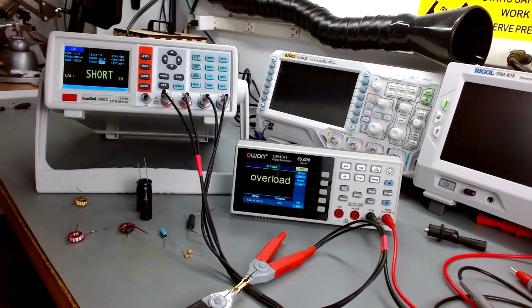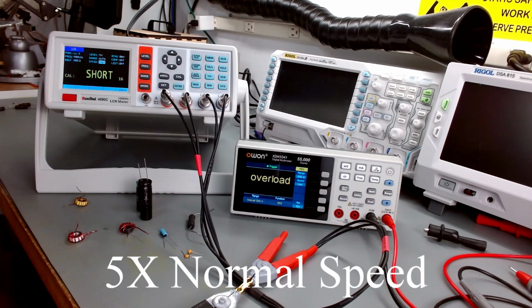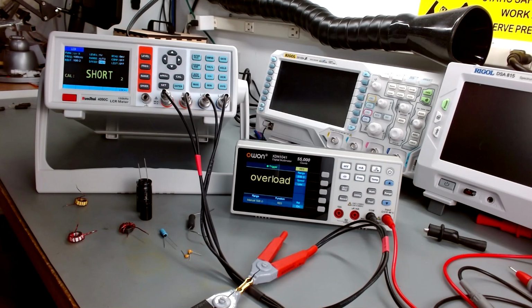You can see it goes to calibration. It says I'm shorted, which you are. It starts a 20 countdown. And now we're going to be waiting about 40 to 45 seconds for that to complete. Okay, that's it calibrated short. You can do an open the same way.